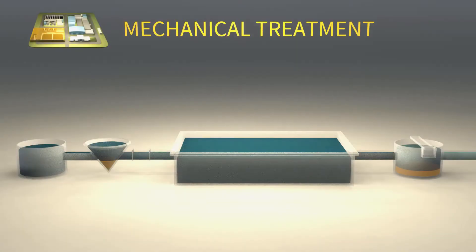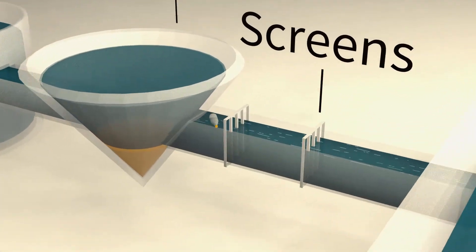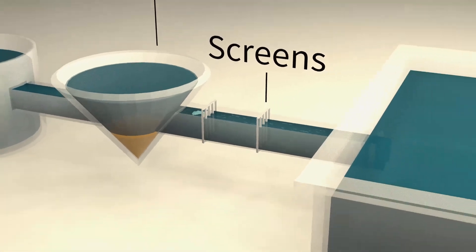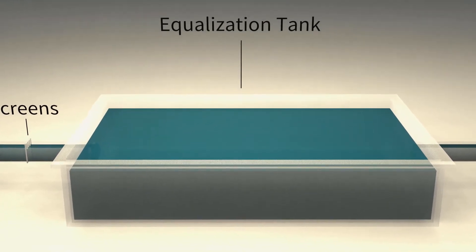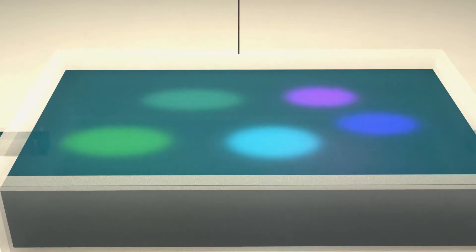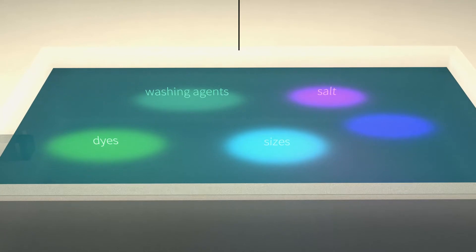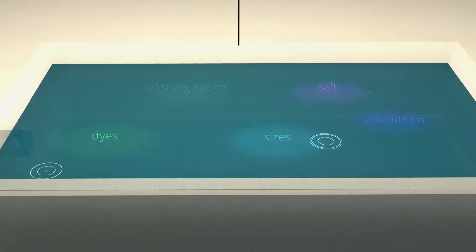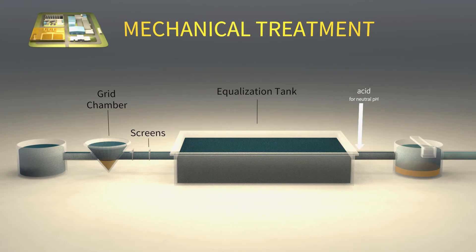In the mechanical treatment, debris and fibers are removed by a grid chamber and screens before the effluent is stored in a buffer and equalization tank. Since textile facilities use various processes in their production, the wastewater contains a mixture of chemicals, washing agents, sizes, dyes, salt, and alkaline pH. Dosing acids brings the pH to neutral, and coagulants help suspended solids settle in the primary clarifier.